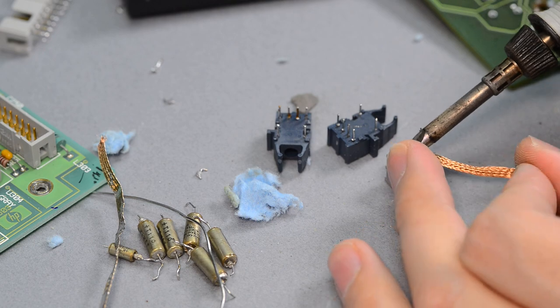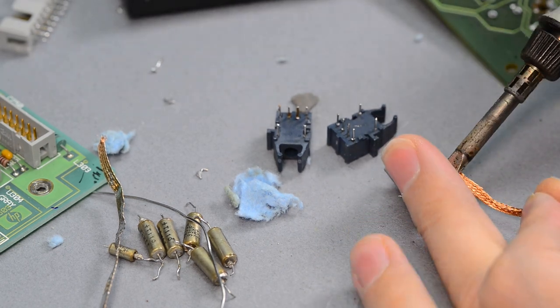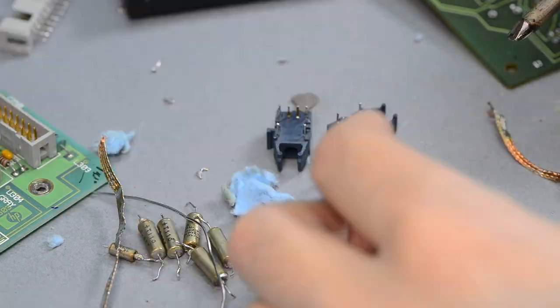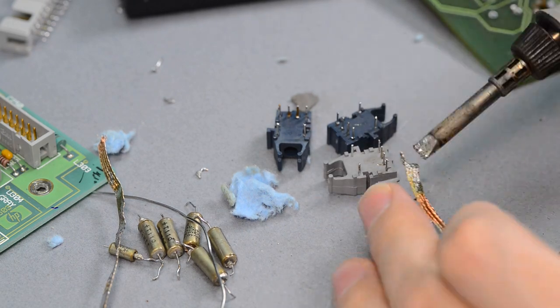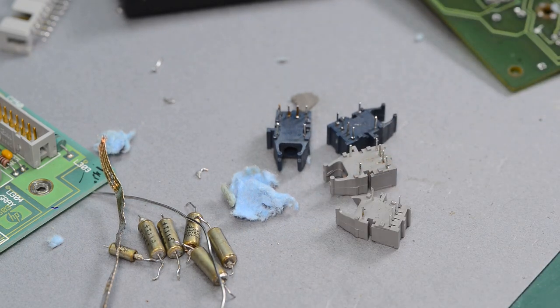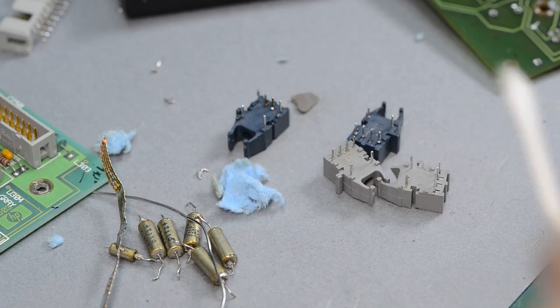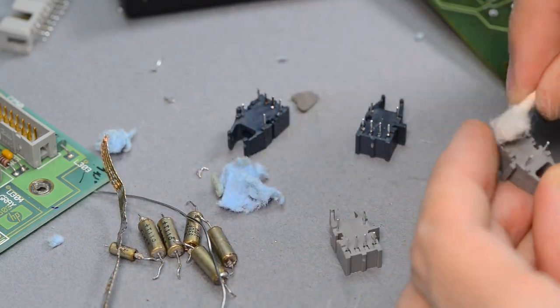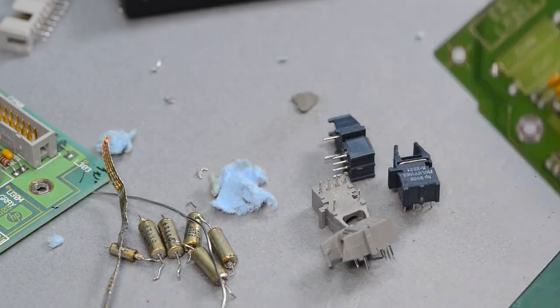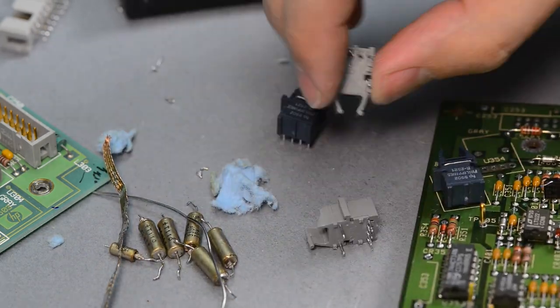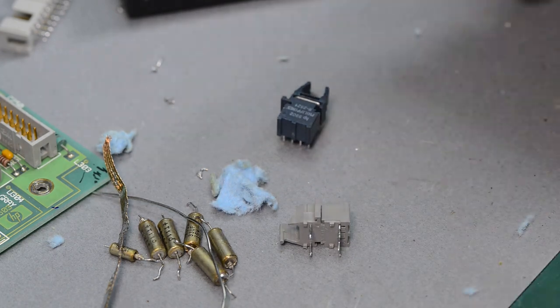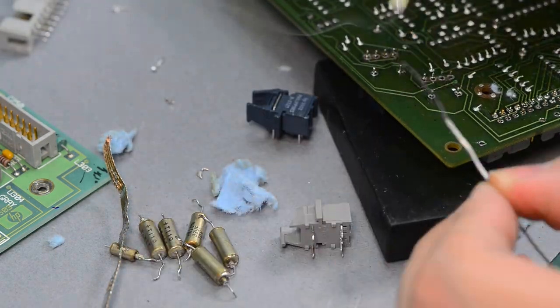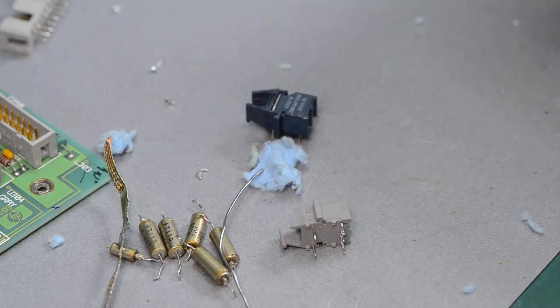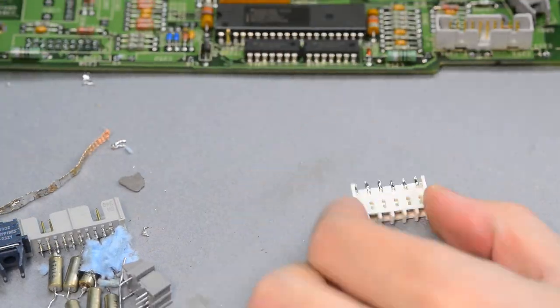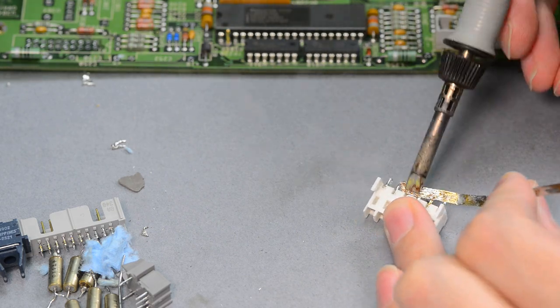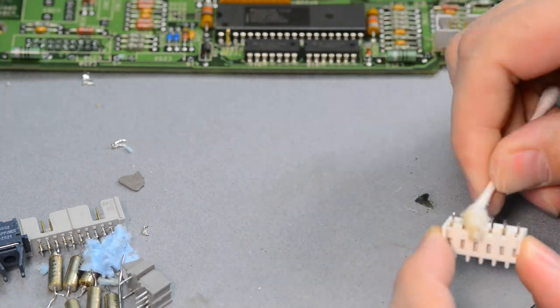So a little bit of history on this board that I am working on. It was tested before in another 3458A, about a year or so ago. This board came from a faulty meter, and it was tested with the result of drift around half a ppm per hour. So even if you are using ACAL, it would be pretty much useless since the instrument with this A2D would not be able to meet even 24-hour transfer specifications.